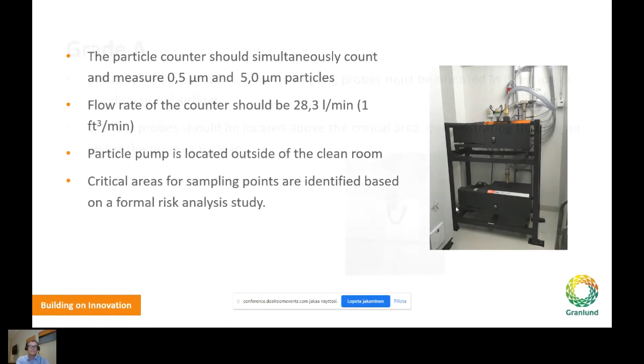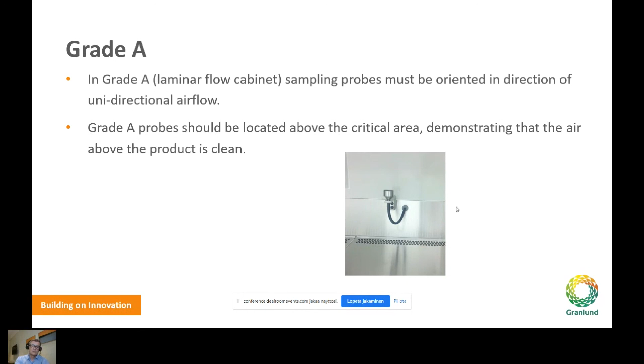Here is an example of a grade A sampling probe. It must be oriented in direction of unidirectional airflow and also be located above the critical area, demonstrating that the air above the product is absolutely clean.